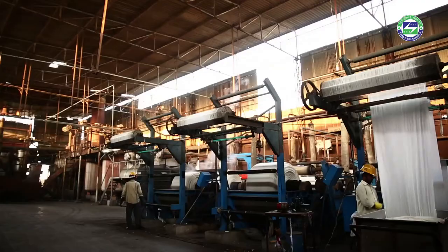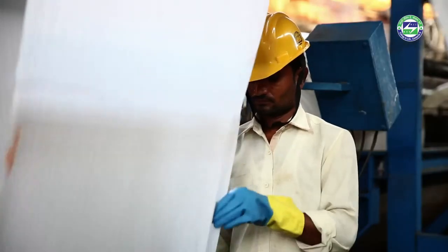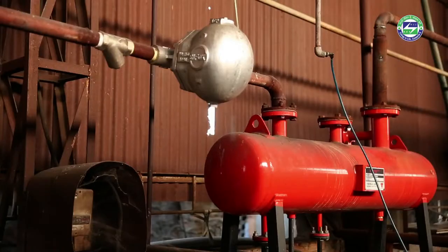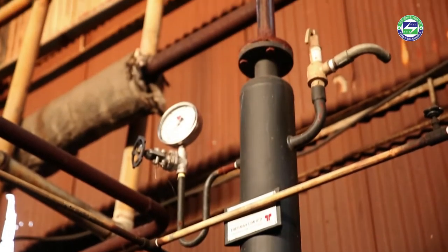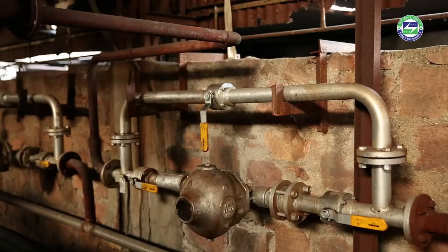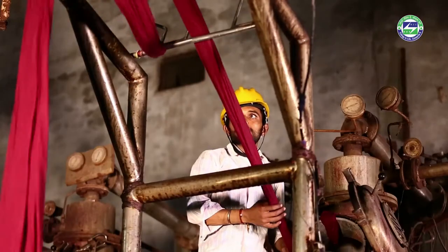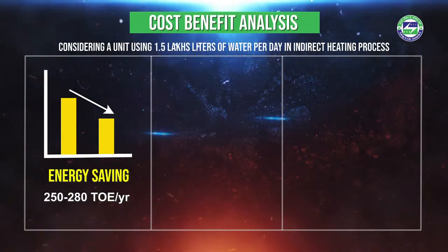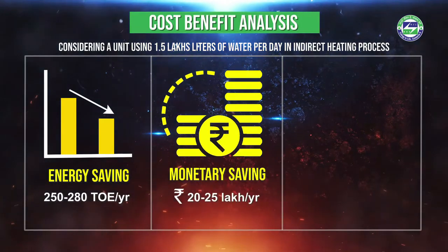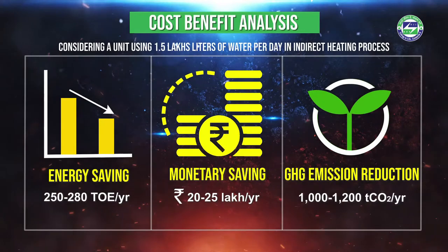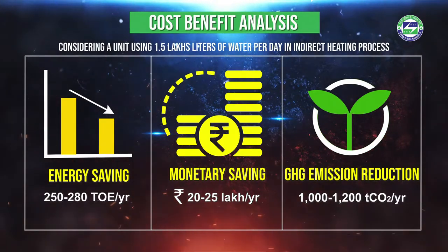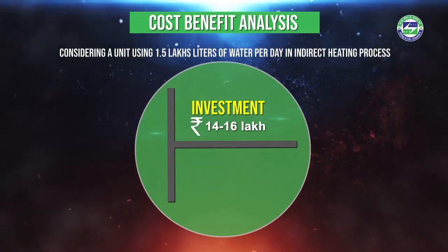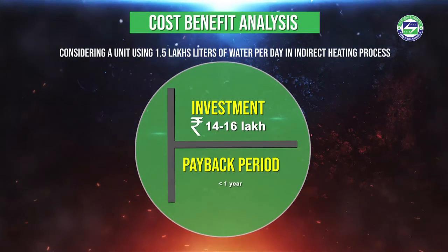To understand the cost-benefit analysis, consider a unit using 1.5 lakh liters of water per day in an indirect heating process. The installation of the condensate recovery system would lead to fuel savings of around five hundred tons and water savings of around one thousand kilolitres. This implies energy savings of 250 to 280 tons of oil equivalent, monetary savings of rupees twenty to twenty-five lakhs, and GHG emission reduction of one thousand to twelve hundred tons of CO₂ per year.